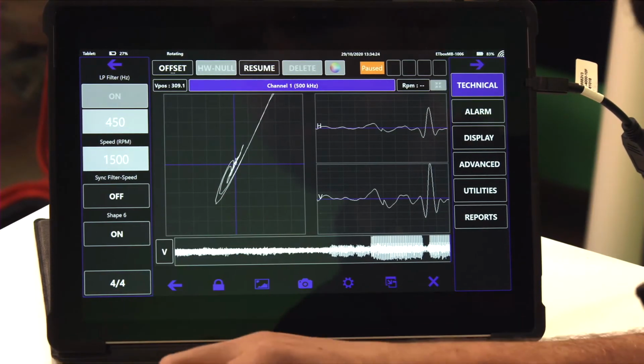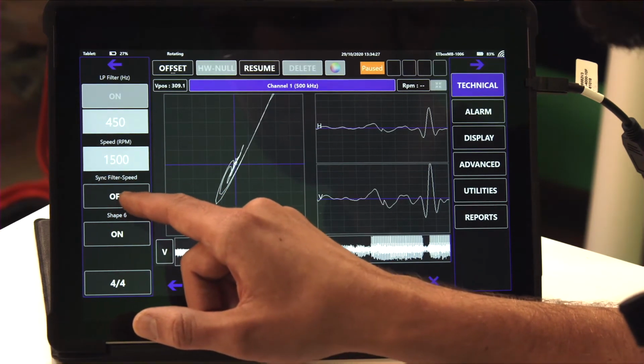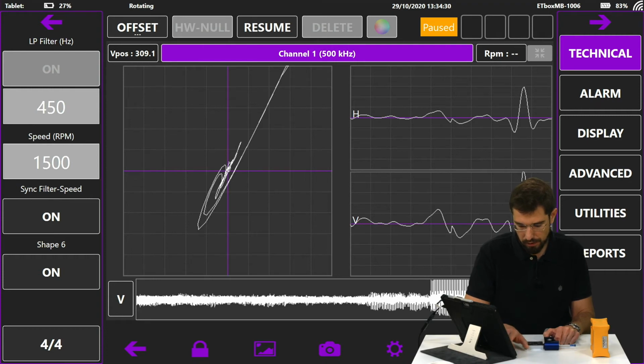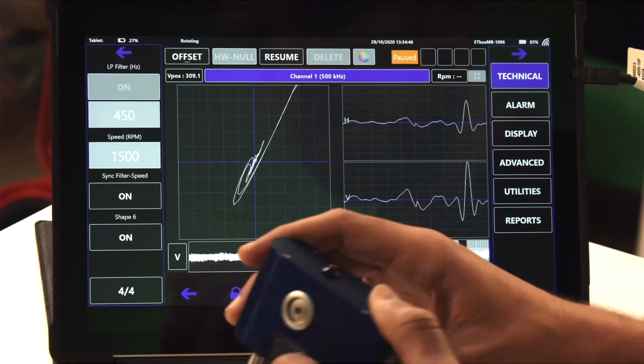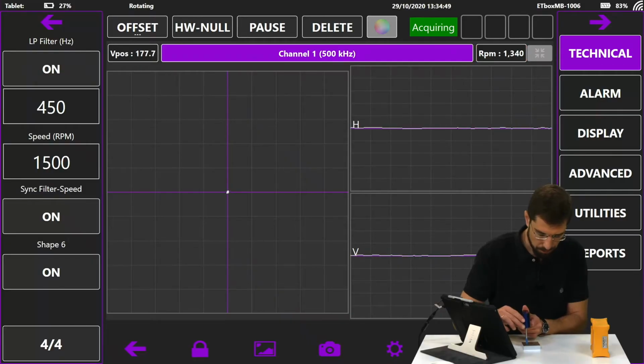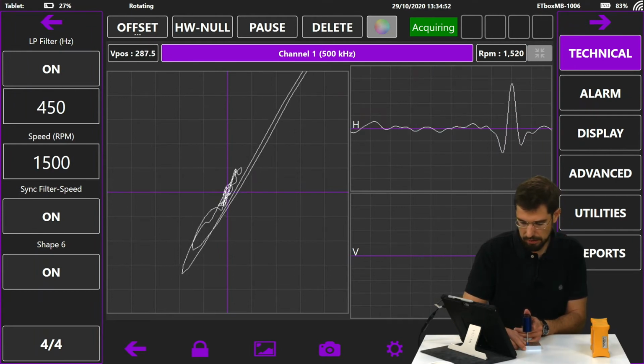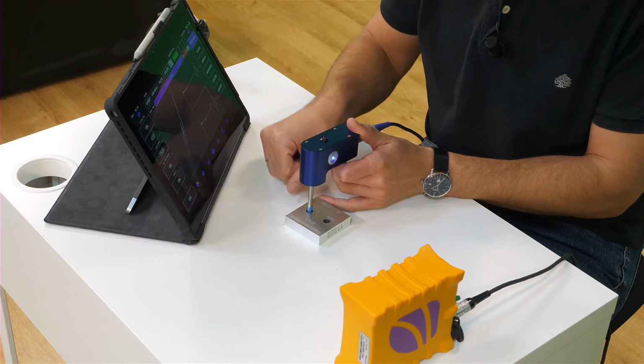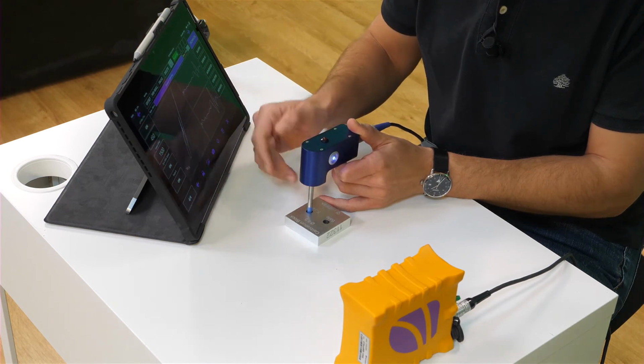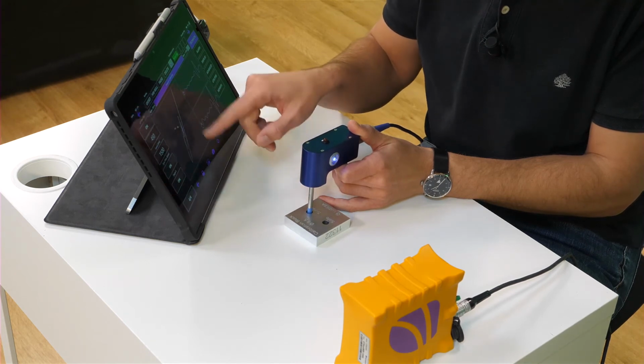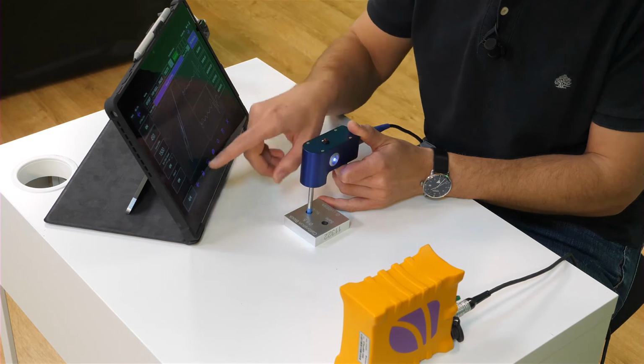I want to explain to you are, first, the sync filter speed, which right now is disabled. If we activate it, what we get is that once we change the rotation speed, both the high pass filter and the low pass filter are automatically calculated following some charts contained in the instrument. And we are going to connect the Shape 6 button, with which we can get the shape of the signal to be one that operators are generally used to. It's a signal with a crack that makes a 6 shape.